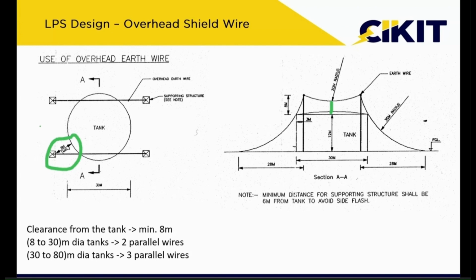The standard has also provided how many masts are required for protecting the tank for various diameters. If the tank diameter is up to 30 meters, we need only two wires. But if the tank diameter is between 30 meters and 80 meters, then we require three, so we may require one more wire at the center portion. This arrangement is more than sufficient for protecting tanks up to 80 meters in diameter. So these are the three different methodologies suggested by the standard for protecting these tanks from direct lightning strikes.